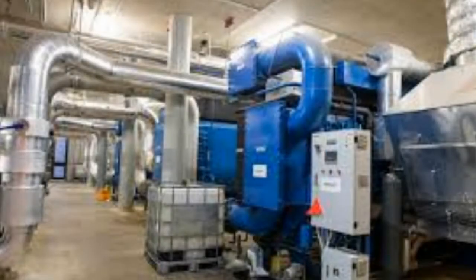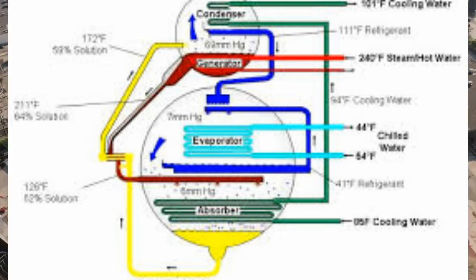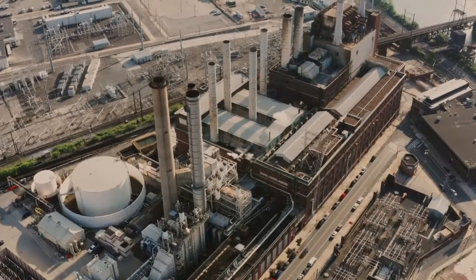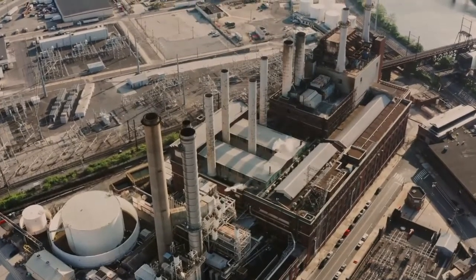The range is sized from 20 to 1500 tons. The Absorption Refrigeration Cycle differs from the Vapor Compression Refrigeration Cycle in that the compressor is replaced by an absorber, pump, and generator, while the condenser, expansion device, and evaporator remain the same.